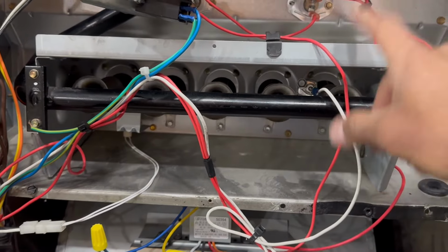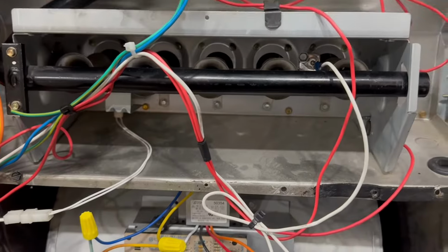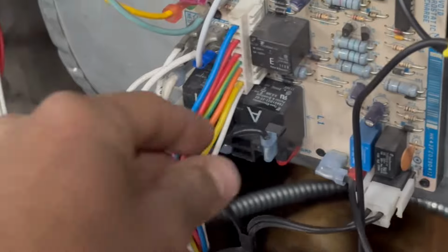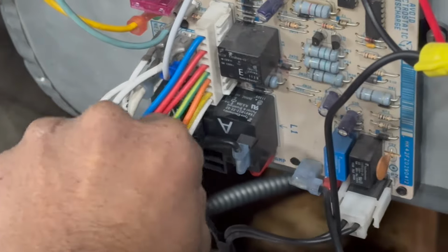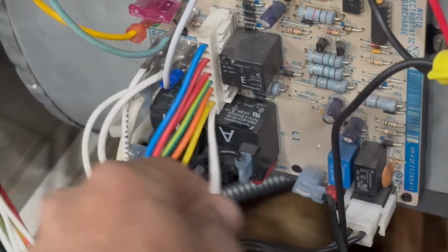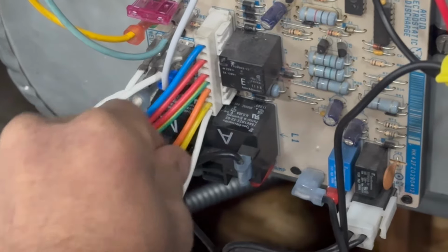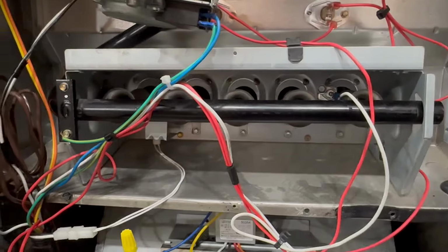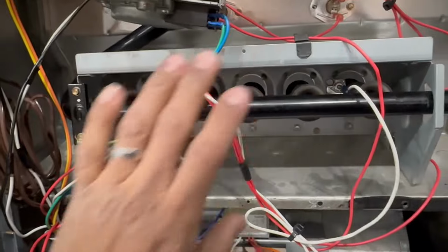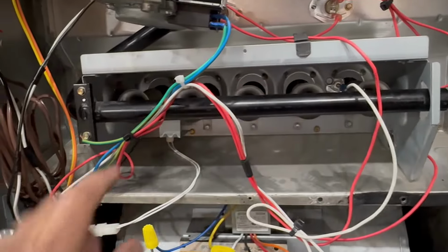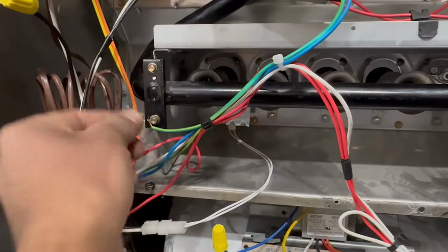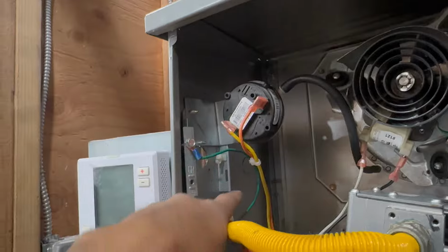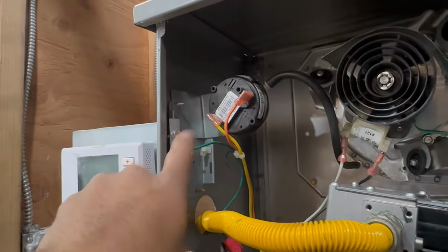So that is why it's important that this is grounded, because that is why down here, you see, on that plug that we were talking about earlier, we have a ground, and then we have the flame sensor, right? This is the one that sends 80 to 100 volts, and we got our ground here. So that helps us to complete the circuit, but it's important that this part here is grounded. So any furnaces that you're working on, you got to make sure it's grounded. And what I mean by that is, you see this part here? That's grounded. So that's good. And then the ground coming from the pigtail, from actual power from the outlet, it's also grounded.